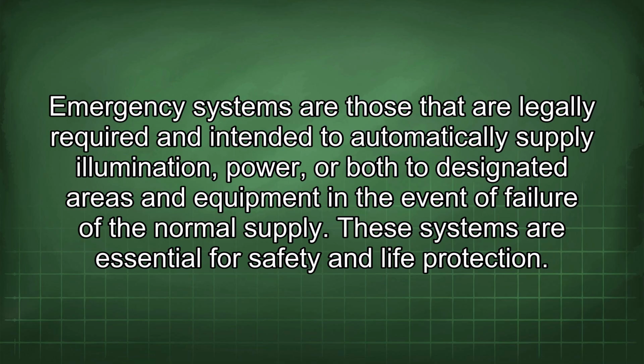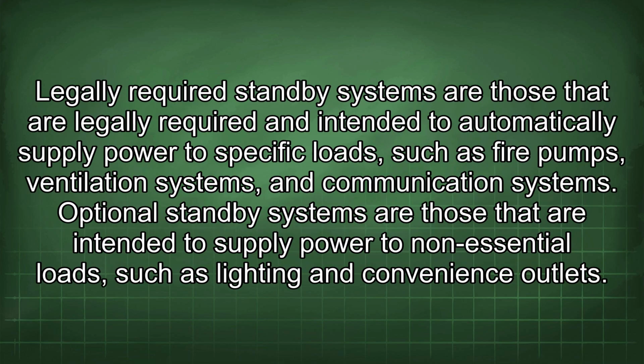Emergency systems are those that are legally required and intended to automatically supply illumination, power, or both, to designated areas and equipment in the event of failure of the normal supply. These systems are essential for safety and life protection. Legally required standby systems are those that are legally required and intended to automatically supply power to specific loads such as fire pumps, ventilation systems, and communication systems. Optional standby systems are those that are intended to supply power to non-essential loads such as lighting and convenience outlets.